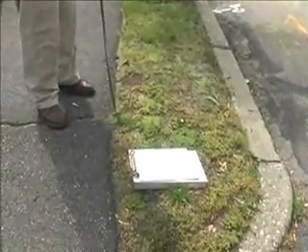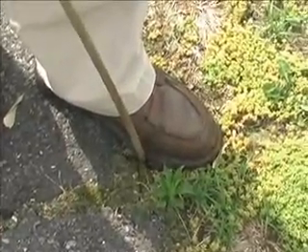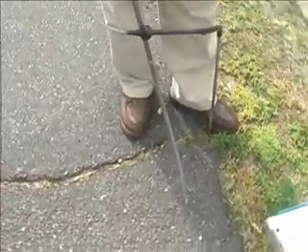Let's try over here. We had a higher gas reading here, and something under there, so we'll stop right there. You'd feel it, but that's okay. We'll still take a reading here. It's a little bit shallower, but could be an old tree root. There's no mark out here. Actually, looking at the sidewalk, it probably is the tree root.